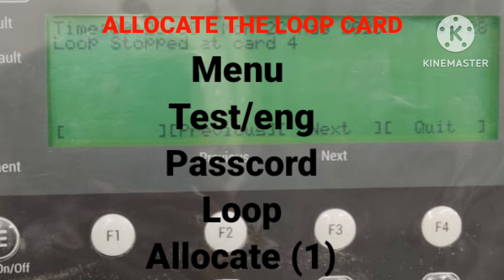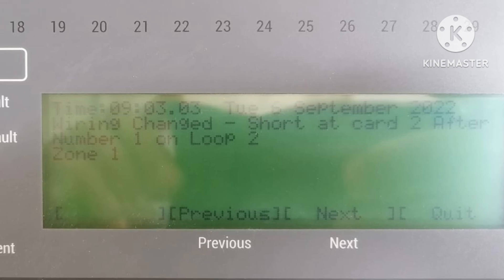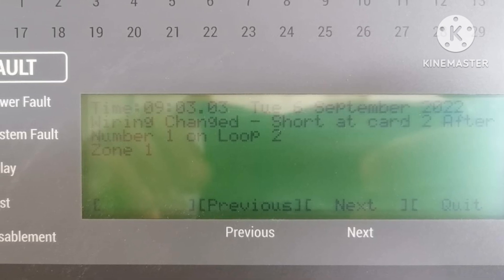After allocation stops at a particular device, you have to check that device. Sometimes there is no physical short, but the device is damaged. Open the wiring from the base termination and remove the device. If in that case it still does not relocate, try to isolate the short another way. It may also be that the loop card itself is damaged.